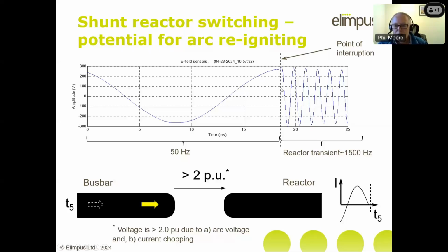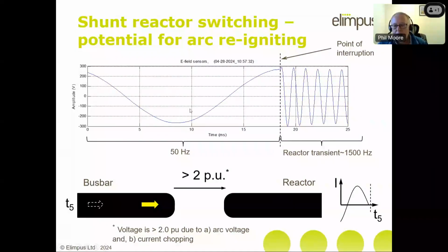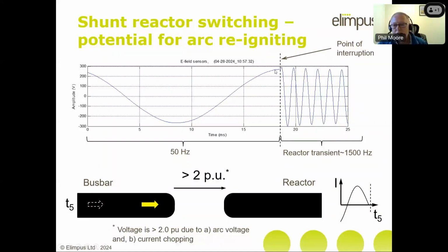And the reason that that's a problem is that if you look at the point of interruption, if we go about half a millisecond beyond it, then the system voltage, the bus bar voltage, is going to be pretty much the same. It's just going to be the peak value there. But if you have a look at the reactor terminal, at about half a millisecond later, it's gone almost to the negative value. So we're now seeing roughly 2 per unit across this break. And that's why it is so difficult to interrupt shunt reactors, because as soon as you get rid of the current, you get a very large voltage very quickly across the contacts.